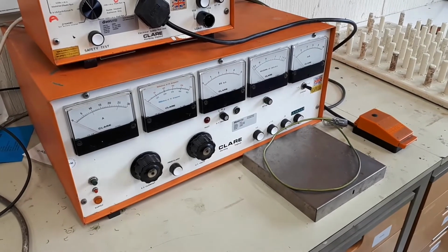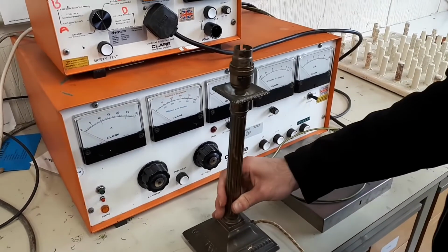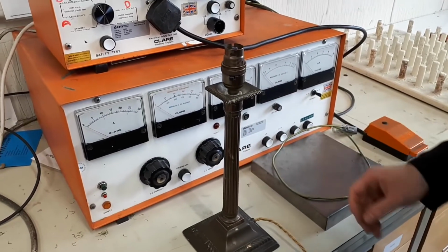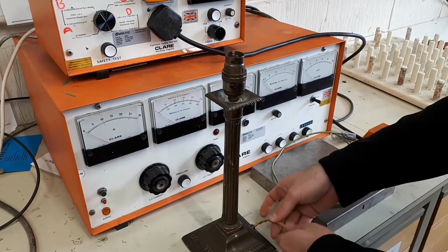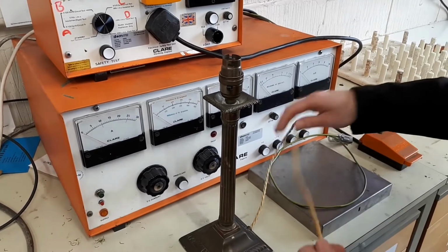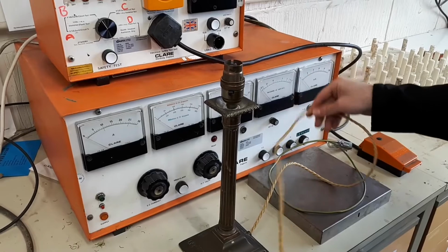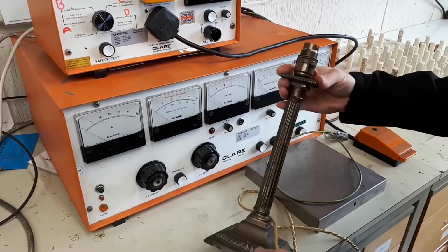Before you test either class 1 or 2 light fittings, you will need to carry out a visual inspection. Check for any damage, including the cable, that would make the fitting unsafe.